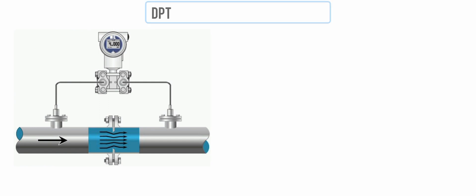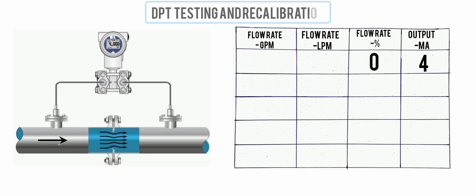Remember before calibrating the transmitter, it must be removed from service. The flow transmitter connected across the orifice produces a current output of 4 milliamps at 0 liters per minute and 20 milliamps at 189 liters per minute or 50 gallons per minute.